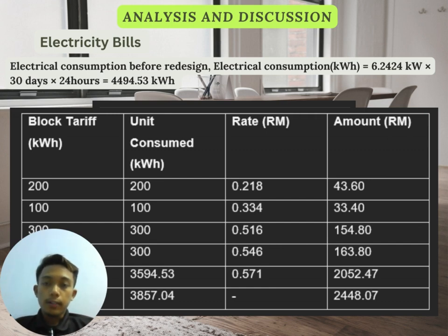This is how to calculate the electrical consumption before redesign. The electrical consumption equals 6.2424 kilowatts, which is the maximum demand before redesign, multiplied by 30 days, multiplied by 24 hours, giving an electrical consumption of 4,494.53 kilowatt hour.